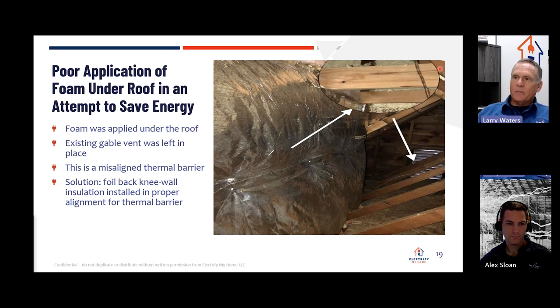a space like this. But you can see they left the attic open here, which broke that pressure boundary. So it did no good for them to raise the thermal boundary to under the roof. It had absolutely no influence. Might have been reducing the BTU transfer through the roofing material a bit, but the attic was still extremely hot, and it was still a hot attic.